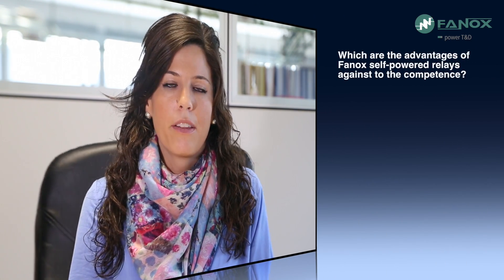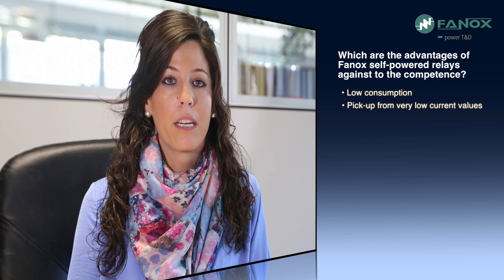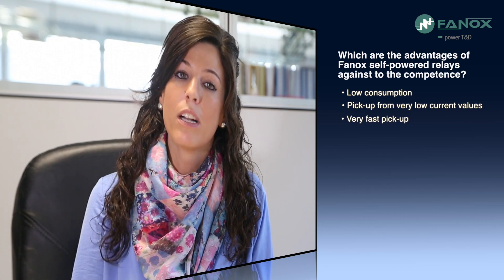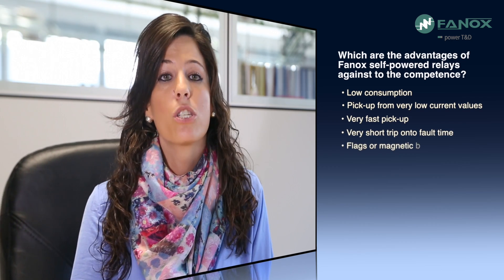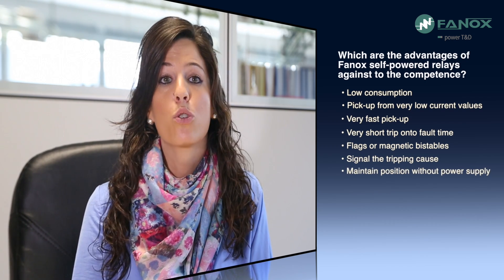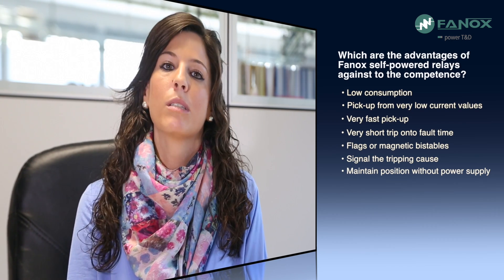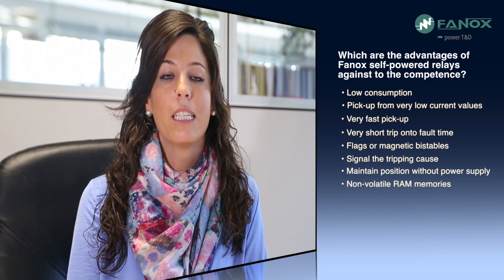The advantages of Fanox self-powered relays against the competition include: low consumption and pickup from very low current values, and very fast pickup allowing a very short trip time to fault. All self-powered relays have flags or magnetic bistables. These elements change their position when a fault occurs and maintain their position even without power supply, making fault situation checking practically instantaneous by simply observing the relay.